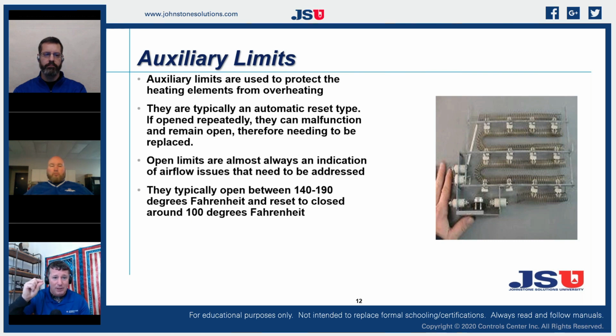Those are also a bimetal style limit. Those are there as an emergency source, right? It hits 150 degrees, which means the temperature rise has gotten too hot. It's there to open up so that it can protect that heating element and those ceramic insulators. When it cools down to 100 degrees, it's going to reset.